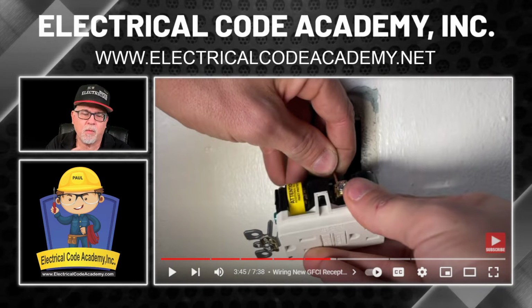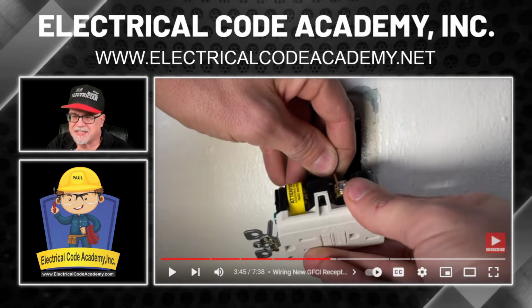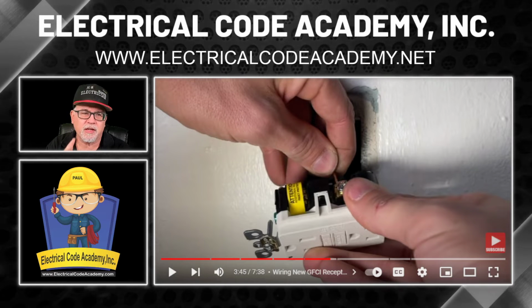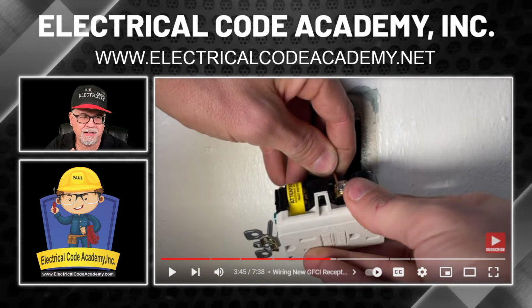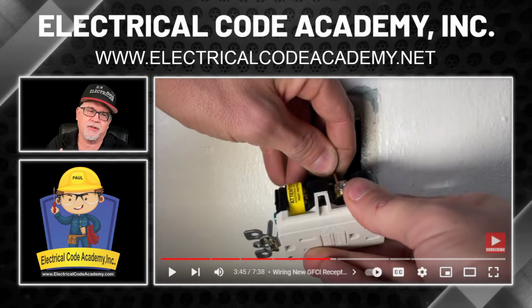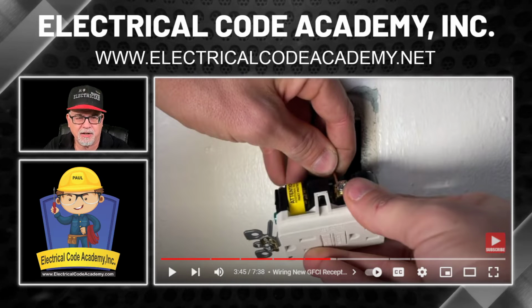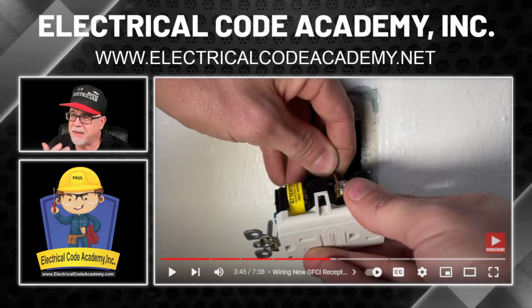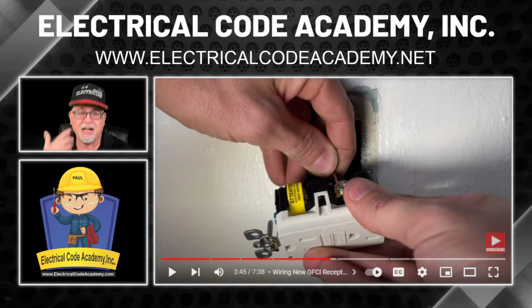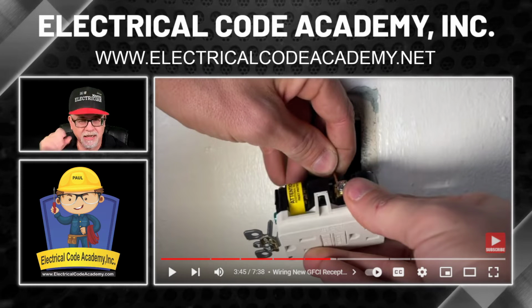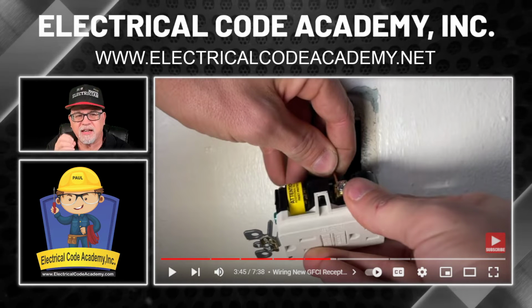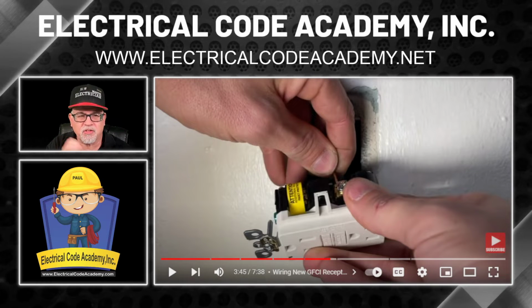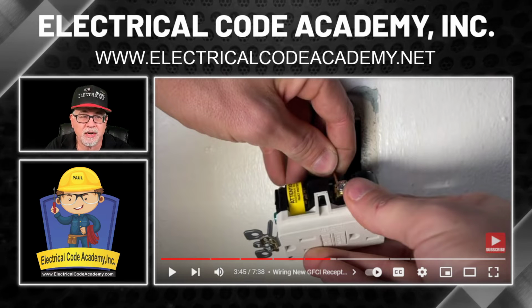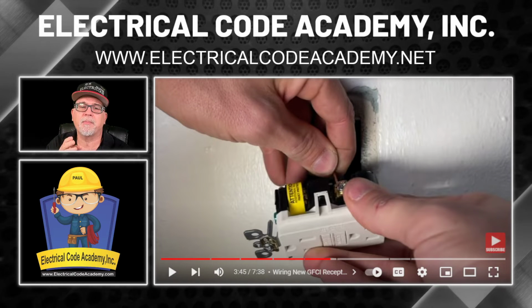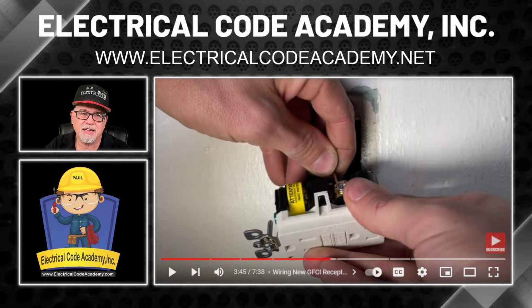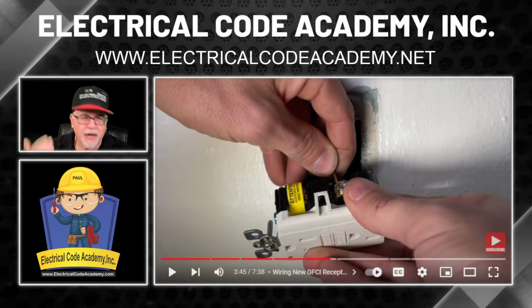But at the end of the day, one of the things that I like to harp on, and again, it doesn't get done, I get it, but you're supposed to be using a torque screwdriver. I know, I can hear what you're saying out there, when everybody goes, Paul, be a practical guy. I'm sorry, I can't, because for years I used a torquing screwdriver, and it was nice. It worked like any other screwdriver. All I did was set it to my value, and it would snap when it gets to the proper torque. Studies have shown that the majority of the failures in a circuit come from poor termination. That can be over-torquing, that can be under-torquing, even something as simple as devices. So I encourage you, get a torquing screwdriver and treat it like your regular screwdriver, okay?